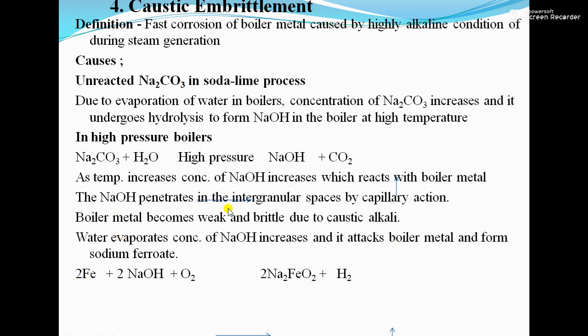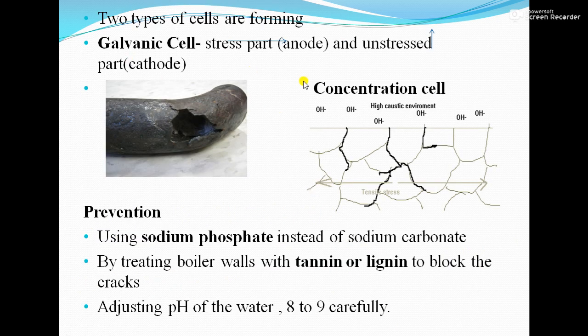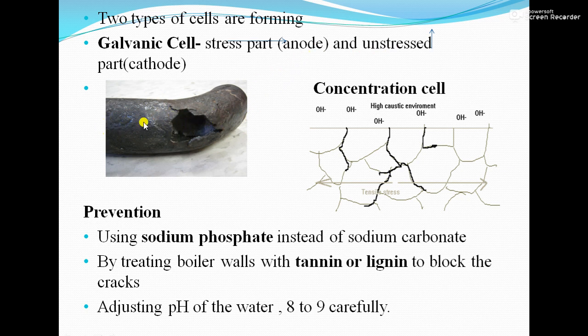There is formation of two types of cells. The first is a galvanic cell: if the boiler metal is bent, a galvanic cell forms between the stressed part and the unstressed part. The stressed part acts as the anode and the unstressed part acts as the cathode, with sodium hydroxide acting as the electrolyte. The anode gets corroded and the cathode gets protected.